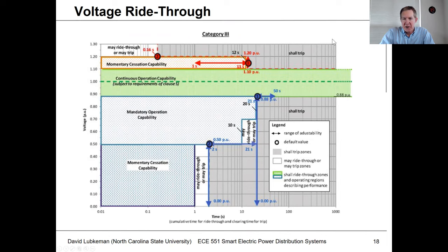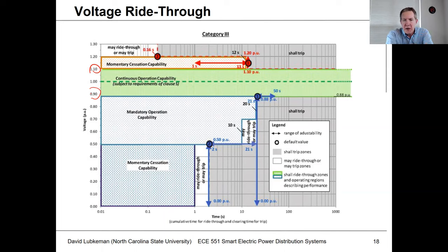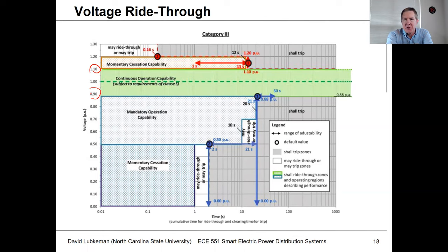Let me try to break this down a little bit. If we have a grid disturbance, we don't want the DER necessarily to trip offline, because if it's a large percentage of our total generation, we can't afford that. There's what's called a voltage ride-through requirement where inverters need to operate a certain way during either an outage or a voltage sag. So basically, what you see in green between 1.1 and 0.9 per unit is the normal operating range. Between 0.9 and 1.1, any inverter interface is supposed to stay connected.